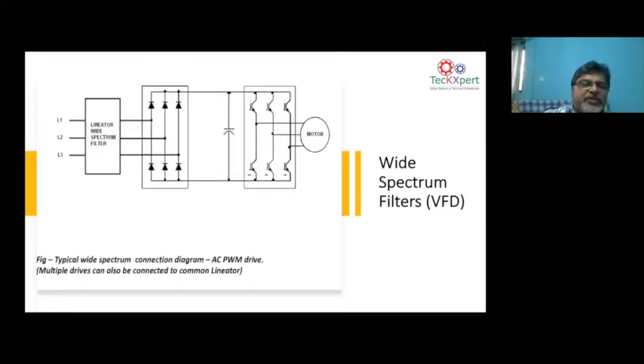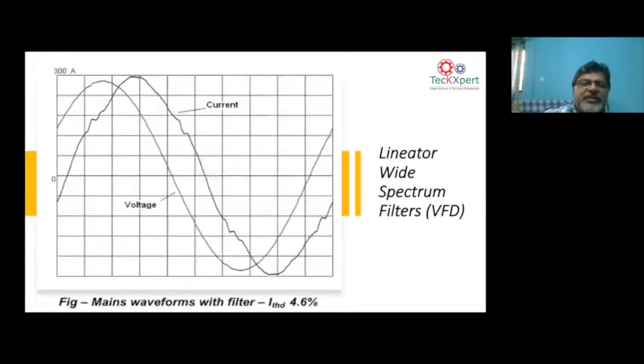If you put a passive filter, these passive filters are like a broadband harmonic filter. What it does is that the harmonics produced by your drive are completely removed at the output of the drive by installing it. This is one of, for example, your HVAC applications. You have your large drives used for chillers and all that. You can put this passive filter and reduce the cost of putting in an active harmonic filter, and reduce the harmonic impact. So this is the concept of passive filters. Go to the next slide.